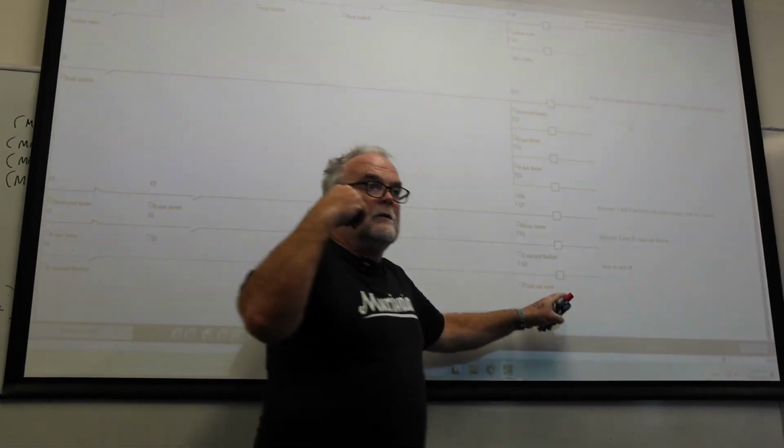Okay, let's run it and we'll see what happens. So I reckon this is what we should see. We should see the things filling up and then our float switch. When I hit the float switch, we should see a 3-second wait. Then we should see our motor come on. Then we should see a 3-second wait, and then we should see 1, 2, 3, 4 pulses. If it's all going to plan. Should that be normally closed? T5? Yep, so one normally closed, one normally open.